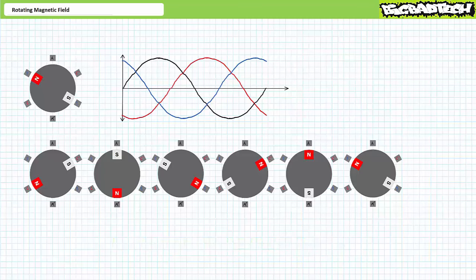Swapping two phase sequences results in the complete reversal of the rotating magnetic field. This method is often used in reversing motor starters — a type of bidirectional motor control circuit where a given phase sequence establishes forward operation and a different sequence establishes reverse. Swapping any two phases results in reversal regardless of which two you choose: L1 with L2, L2 with L3, or L3 with L1. So long as you only swap two, the field reverses.